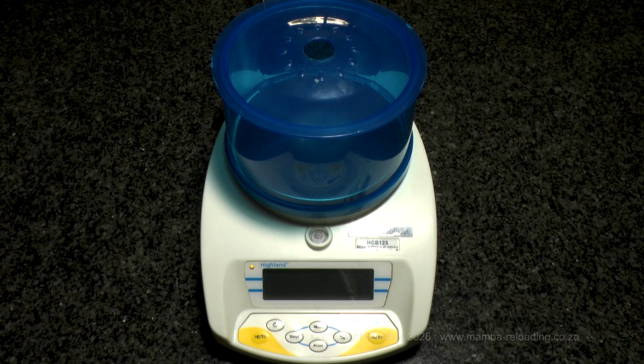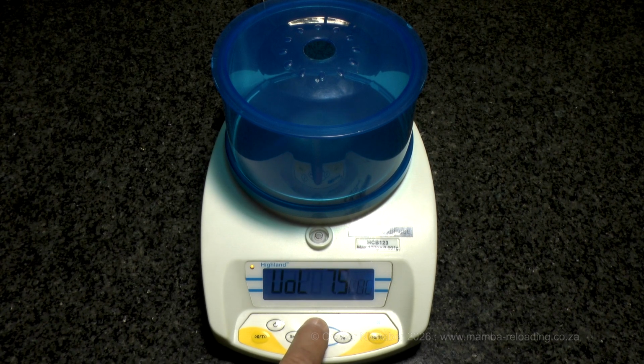To enter the settings menu, press the On button to power up the scale. Then, press and hold the Mode button until F1 UNT is displayed. Each press of the Mode button advances to the next function. Press the yellow Zero/Tare button to enter the first function, F1 UNT. This function controls which weight units are available. Grams, G, is displayed first. Press Mode to toggle the unit on or off.